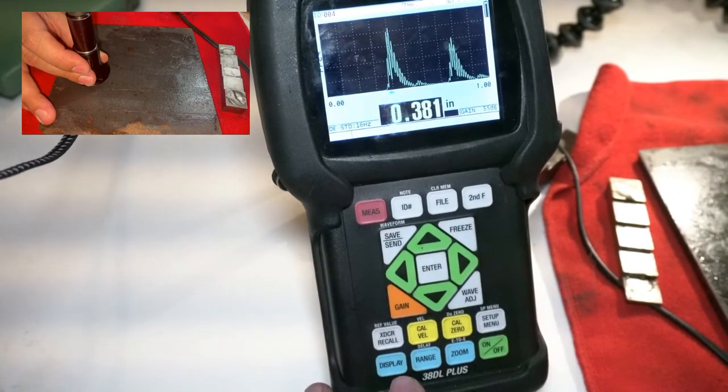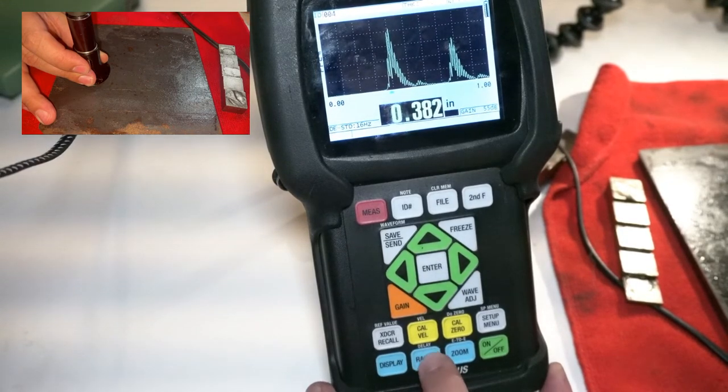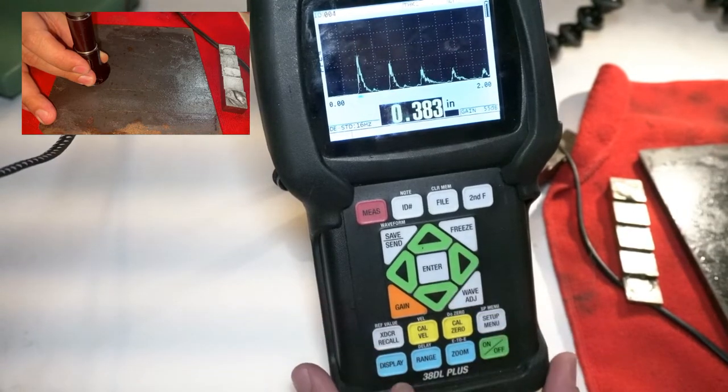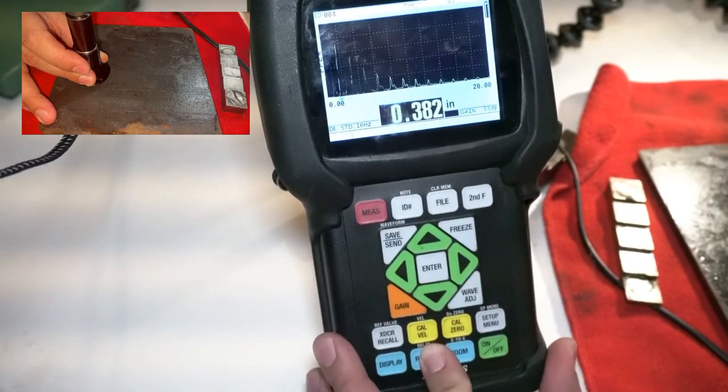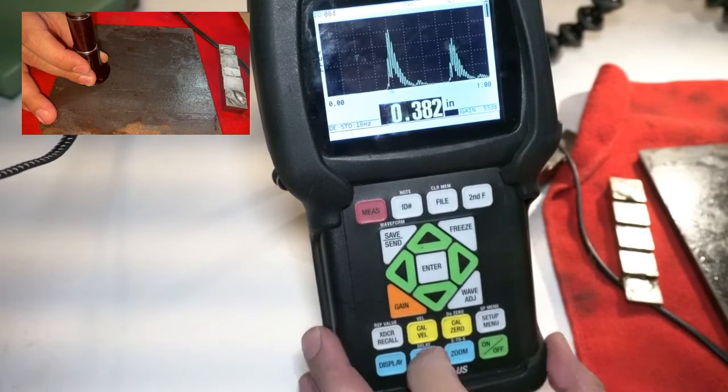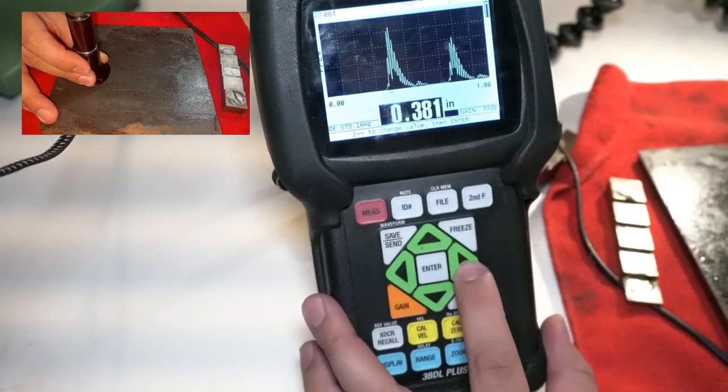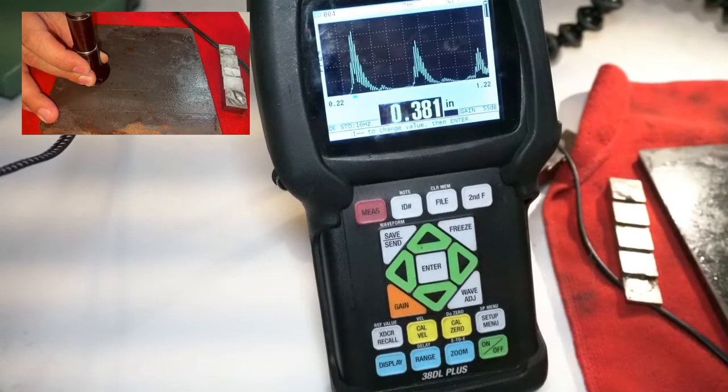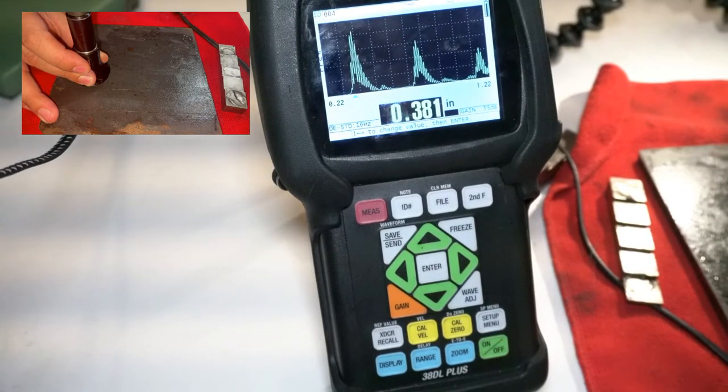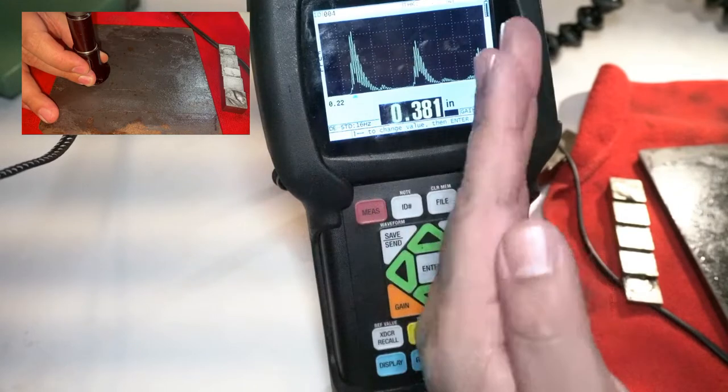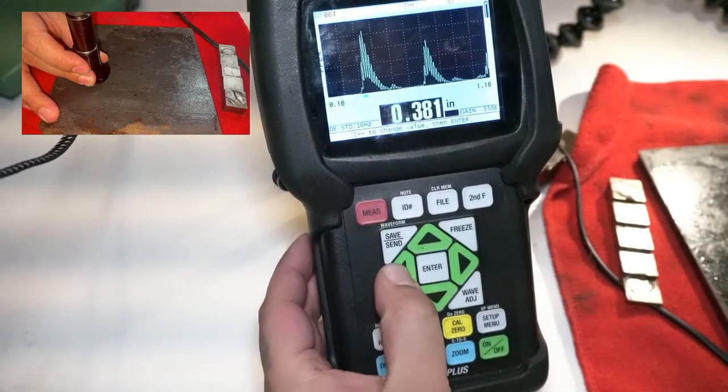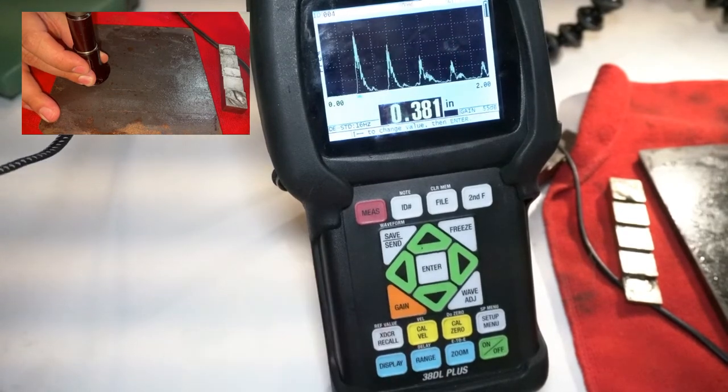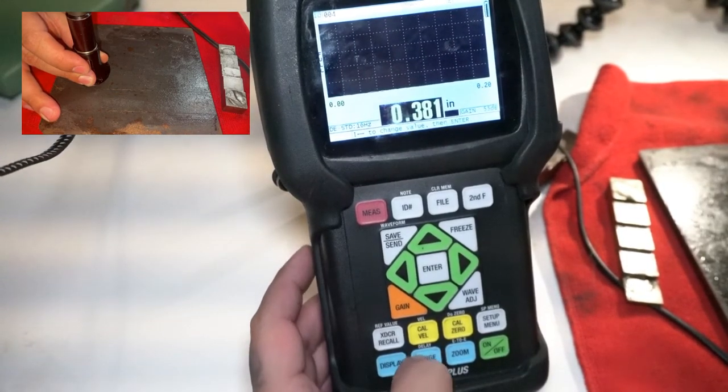Get this wave adjust or extension blank back off the screen. Another great thing is we can actually move this delay out. So if I actually hit delay—whoops, I apologize I hit range there. Let's get back to the one inch range. Second function delay. I can actually move that over and see that third echo back there on that back wall. Again, this is a great tool to use when you're trying to validate a lamination further in time. Just move the echoes over so that you can see its repeat signals. I'm going to take the delay back to zero.